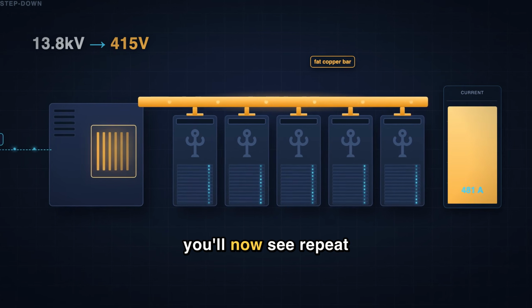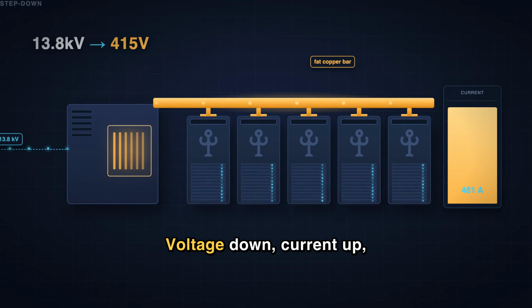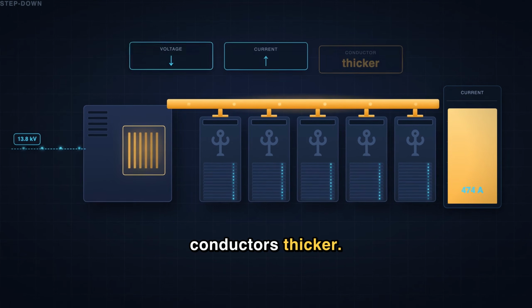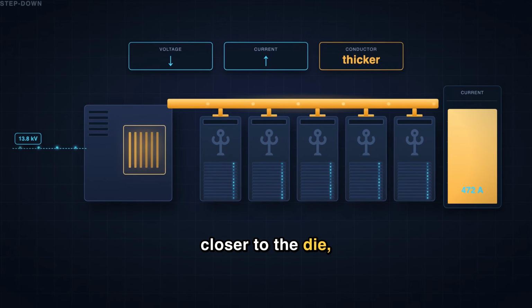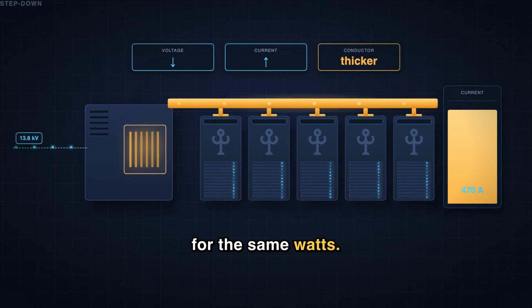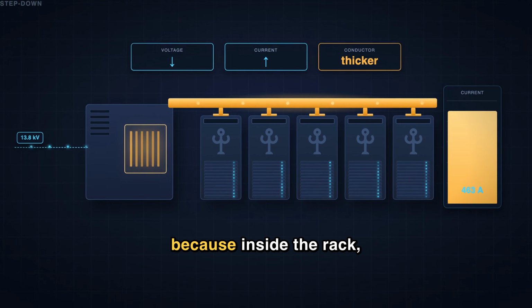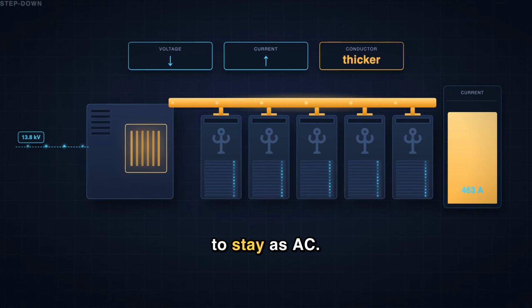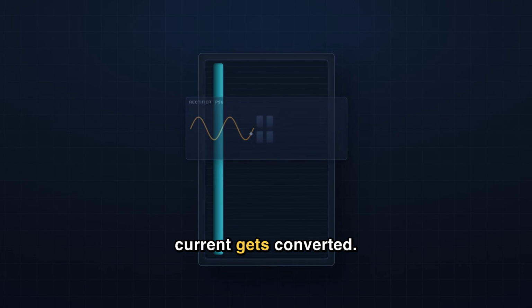This is the pattern you'll now see repeat at every stage. Voltage down, current up, conductors thicker. Each time we get closer to the die, the wires get heavier for the same watts, which sets up the strangest step of all, because inside the rack the power isn't going to stay as AC. Inside the rack the current gets converted.